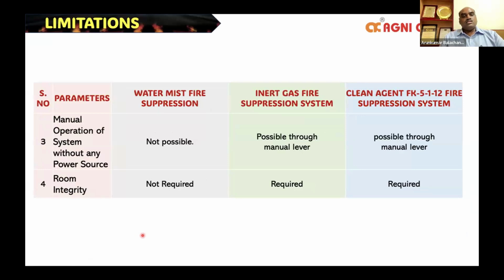The third point is the manual operation of the system without any power source. In a mist system, it is not possible. We cannot operate the motor or the pump without any power source. We need to have either a primary or a secondary power source to operate the pump system. But for an inert or a clean agent, it is possible. We can always manually operate the system using the manual lever in the cylinder valve.